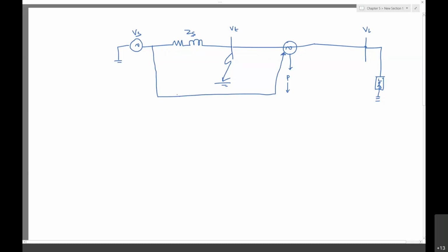Okay, you can't take the power from the source. See, as we mentioned, the series compensator is injecting some amount of real power as well as reactive power. While correcting this particular load voltage, you can't draw this PSC power from the same source. Why? Because this source itself is in a weak condition. Why is it in a weak condition? Because this particular source is experiencing a fault.